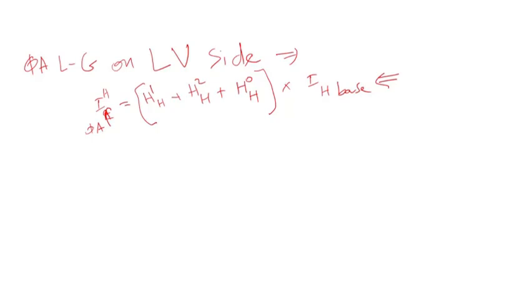Not exactly, the actual winding will be sized, manufacturers would have to calculate the line to ground and three-phase faults, and they will take the worst case, and that will determine how big the conductor or the winding will be. But when the transformer is subjected to a line to ground fault on the low voltage side, the high voltage winding has to handle this current basically.